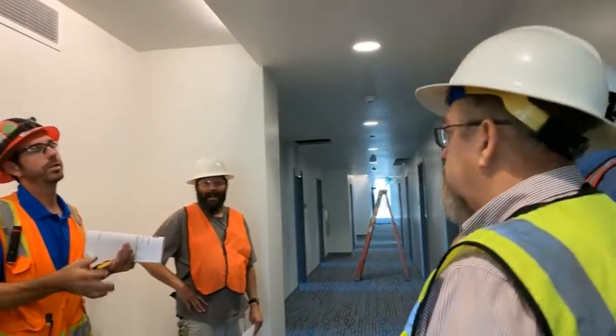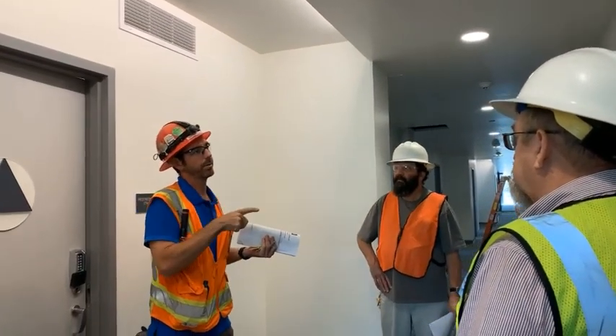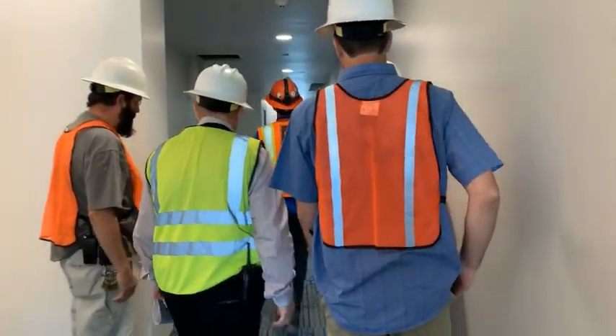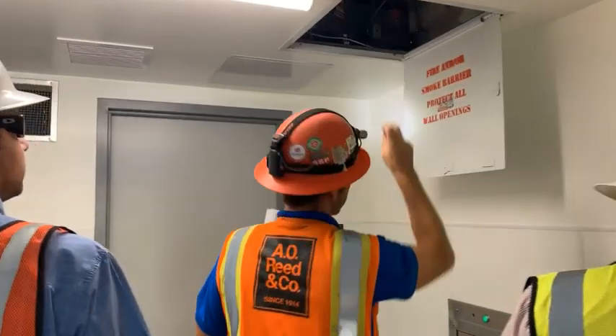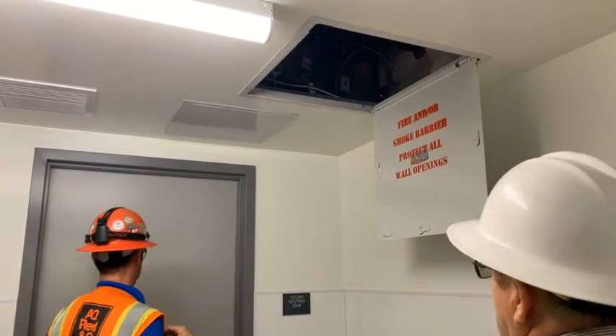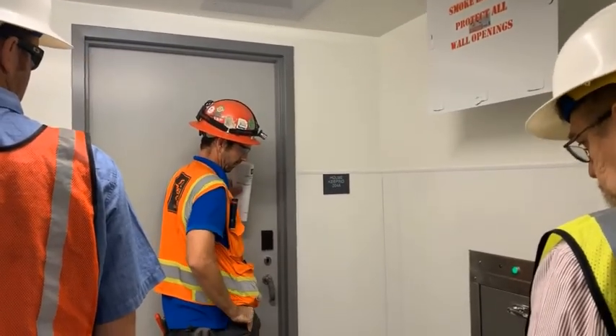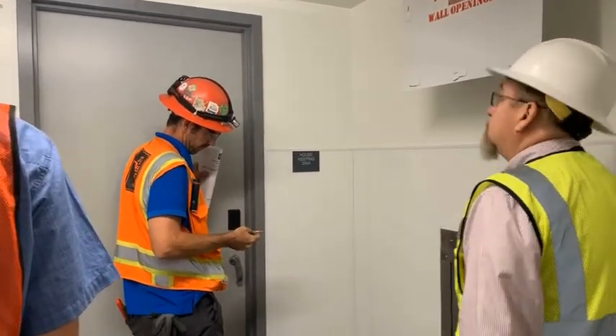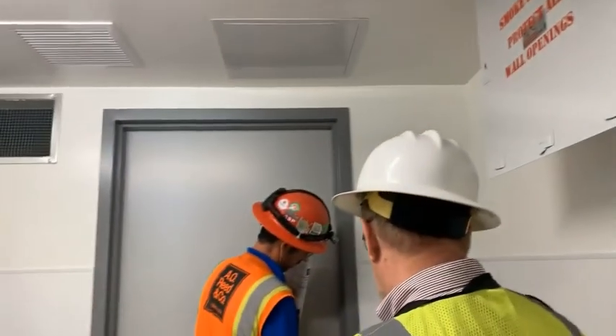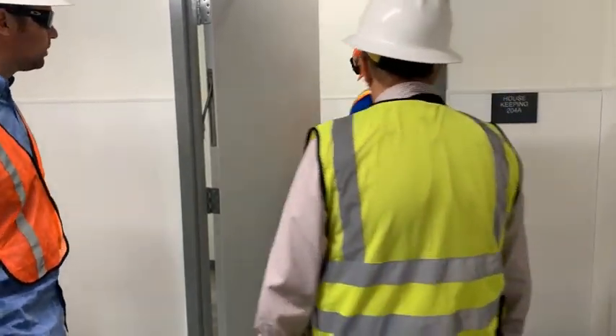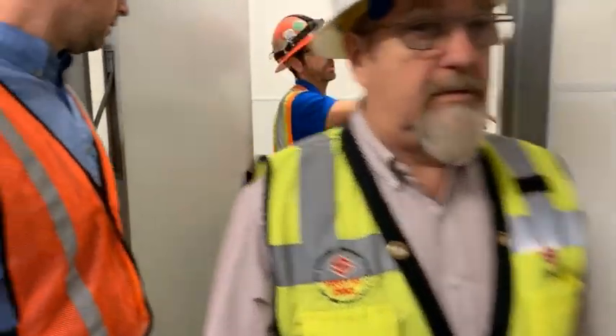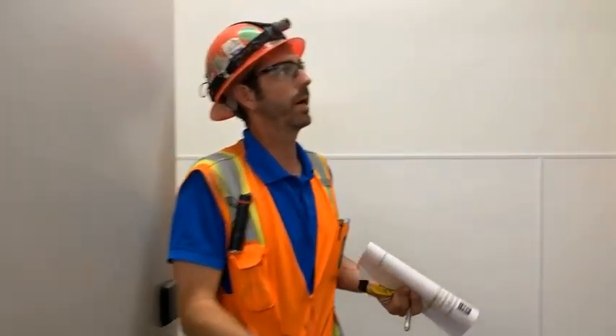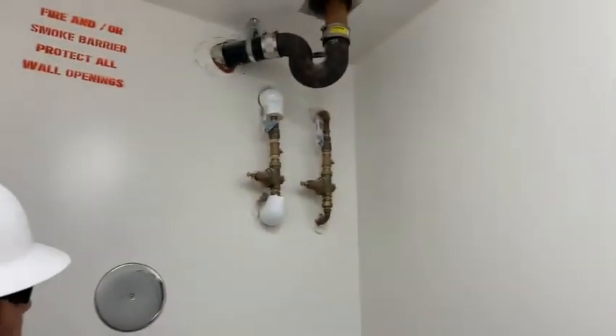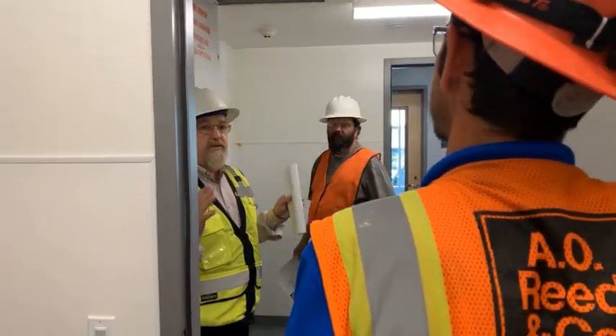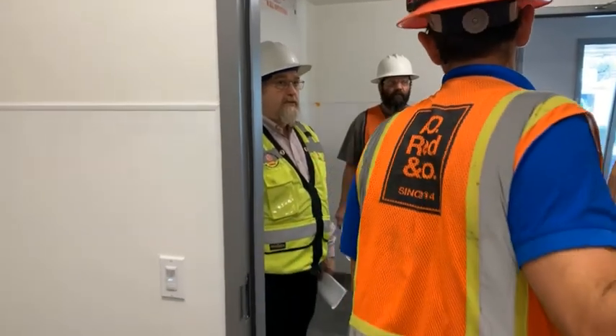Fan coil valves, all these restrooms from here out are all the same. Let's go around the corner. There's a mop sink, there's a janitor closet. Again, we're addressing the no gauges right now, but again, another drop, okay? Own set of pressure reducing valves. All the outlet pressures are always gonna be 45. So any plumbing fixture in the building is 45 PSI, for the showers, for the sinks, everything. Yep. Okay. And that was addressed in an RFI.